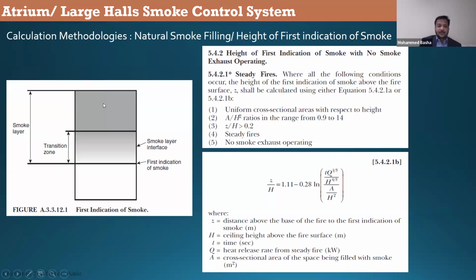If you look at this left side figure, it shows a building. The gray color shows the smoke layer, and the bottom black line shows the first indication of smoke. Below this level is called the tenable condition. This is the hot smoke layer, and this is the smoke layer interface. Here there will be smoke, but it is not as dense as here. That is why it is called the transition zone. Slowly, this transition zone starts to come down to here. When the smoke develops further, the transition zone will be changing, and the smoke layer depth will also be increasing, and the first indication of smoke will be going down. So the term first indication of smoke is the first smoke which comes to the human tenable limit.